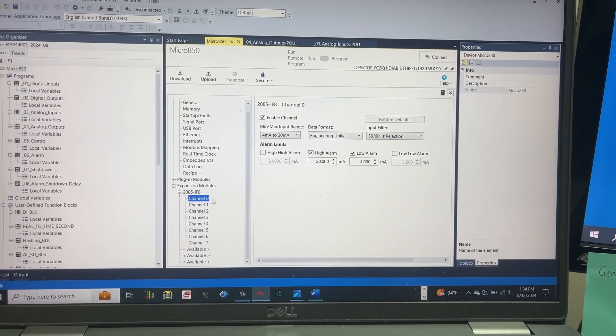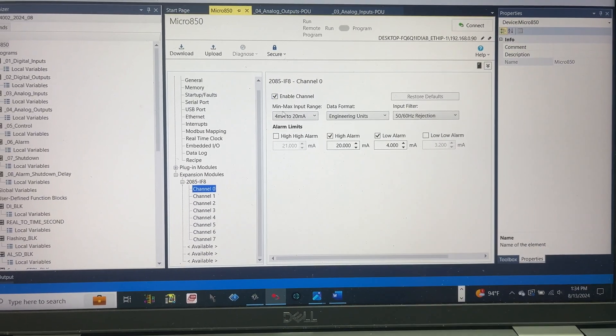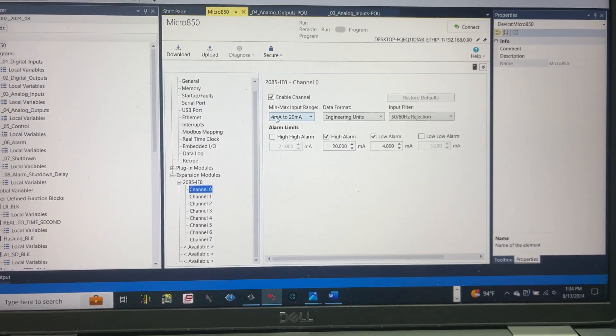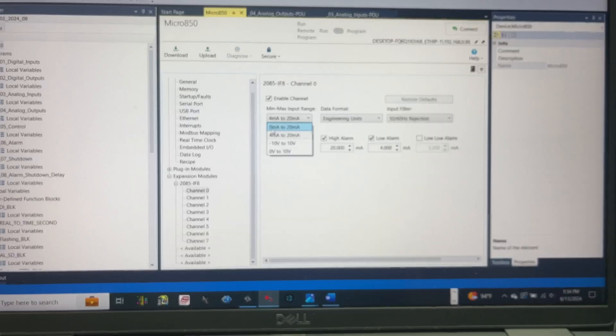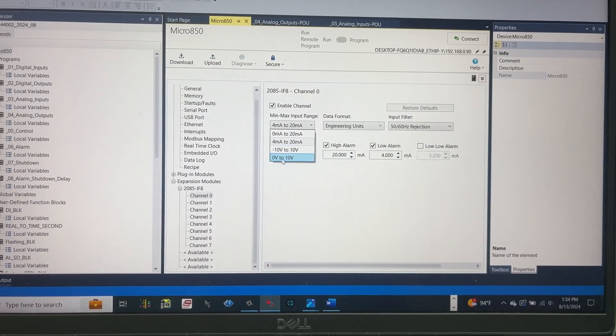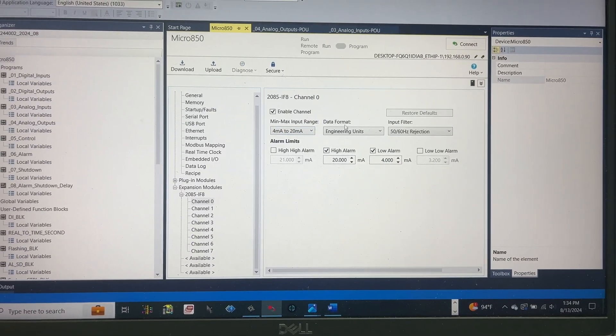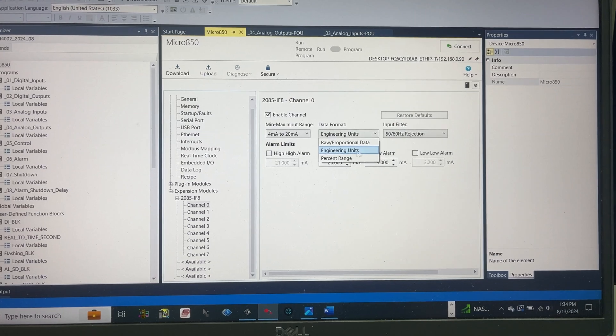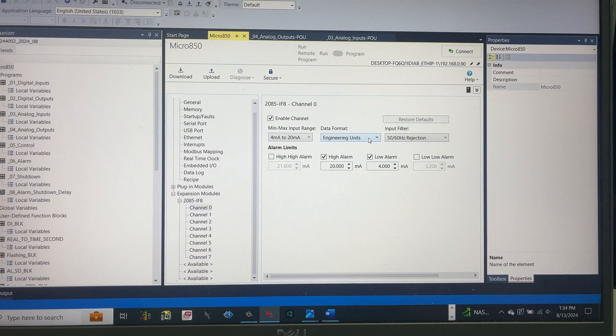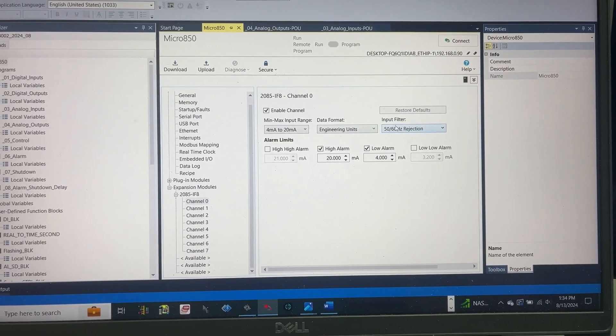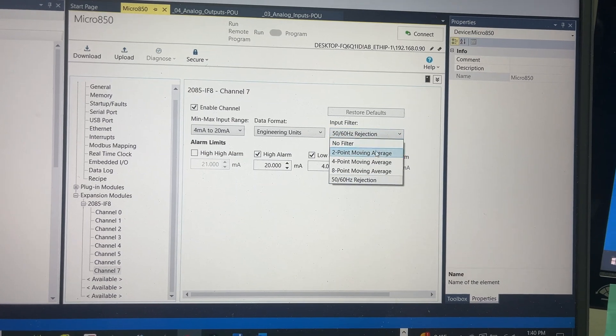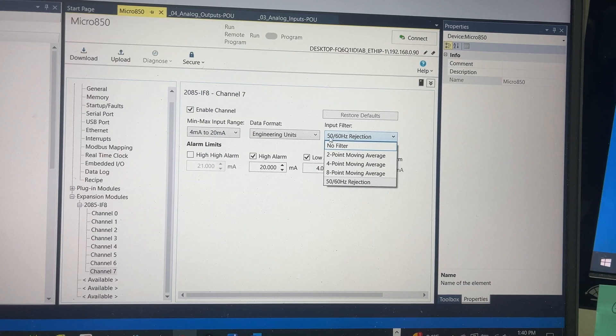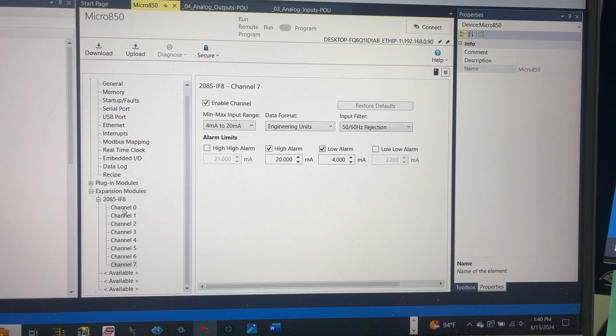For channel 0, for example, enable channel, min max input range 4 to 20 milliamp. Or we can select 0 to 20 milliamp, or minus 10 volt to 10 volt, or 0 volt to 10 volt. Data format can be raw proportional data, engineering units, or percent range. For this video, we select engineering units and input filter. These are all the options available. We are going to go with this one.